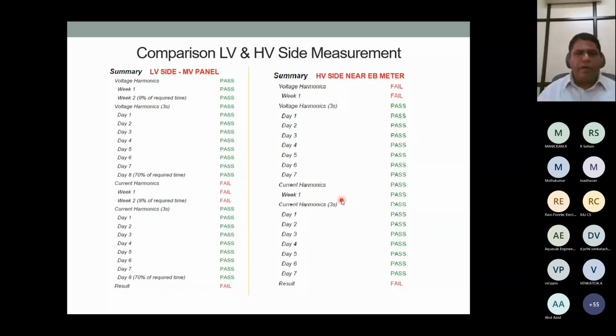So this is a comparison of measurement between the low voltage side, which is our side, the MV panel side, and the HV side. If we put a meter on our side, the current harmonics for which a penalty is imposed will be shown as failed. But if we measure on the HV side, which is the correct point, it will be shown as pass. So the PCC, where harmonics are measured, is a very important subject. We should not measure on the LV side and take corrective actions.